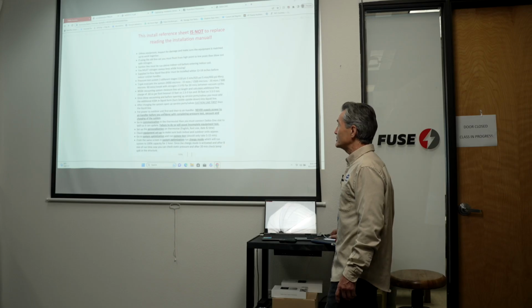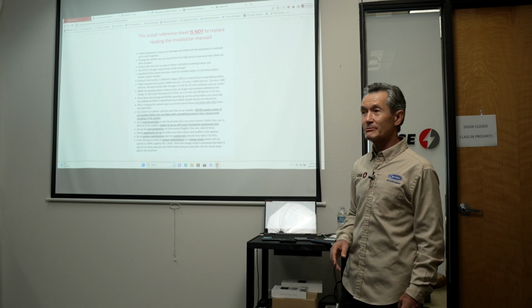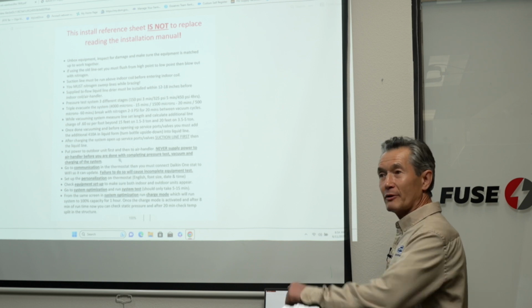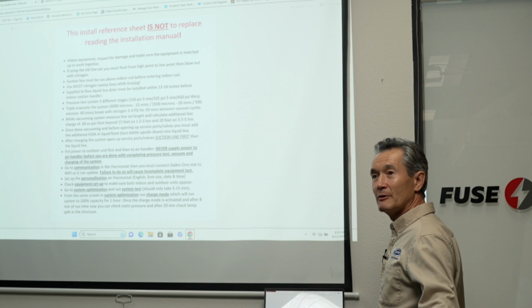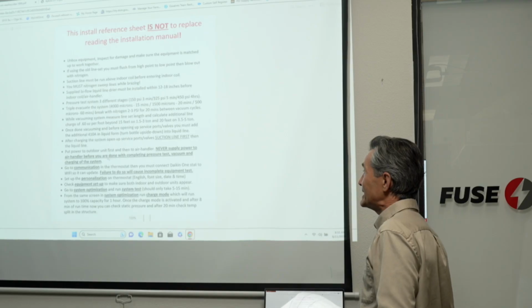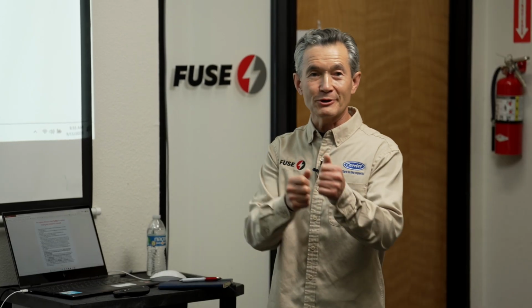I believe we mentioned from the beginning, it is a communicating system. So that's why the data signal goes back and forth. The brain of the equipment is in the outdoor unit, or main brain, let's put it that way, because there are a number of other boards. So that's why it says in here, particularly, firstly, never supply power before completing the installation. This is very important, you have to know, because you're not testing it during installation yet. Completed, only then you can put the power. And it says power the outdoor unit first. It's simple, but you guys have to remember that. Especially when you see on the breaker, right? Outside unit, indoor unit. So that's why always outside unit first.